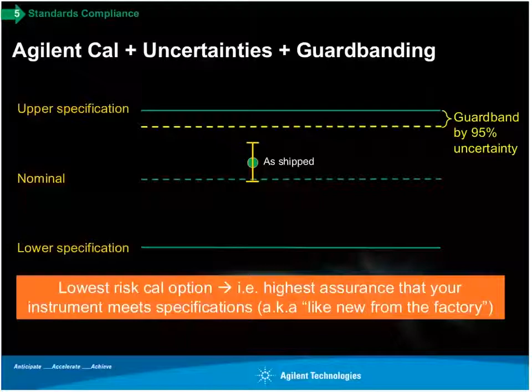This Agilent Cal plus Uncertainties plus guard banding is a service that we have for many of our hundreds of instruments. If this is something you need, when you're speaking with the Agilent service representative, you might want to ask for this particular one. It represents the lowest consumer risk. In other words, the lowest risk to you that when your instrument is returned, it is meeting specifications like it did when it came from the factory.